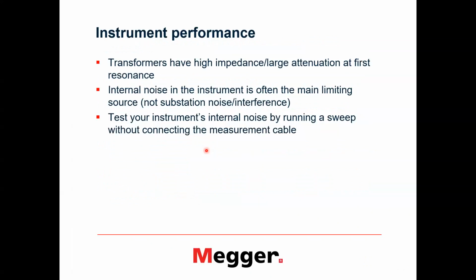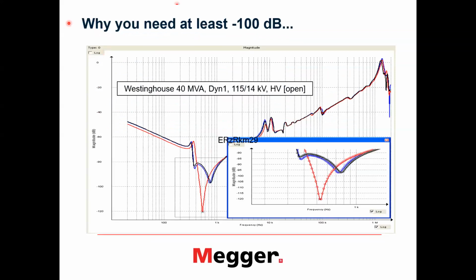And of course, the performance of the hardware inside the instrument makes a difference. If internal noise is too high, then we don't see the very large attenuations and so on. For example, we need at least minus 100 dB of dynamic range, and the noise floor has to be below that. And FRAX has a noise floor below 130 dB. So if we have a large transformer and we measure open circuit conditions, we may have very large attenuations at the SFRA sweep. And in order to properly obtain these results, we have to have a good instrument which allows us to measure this attenuation, not just noise.